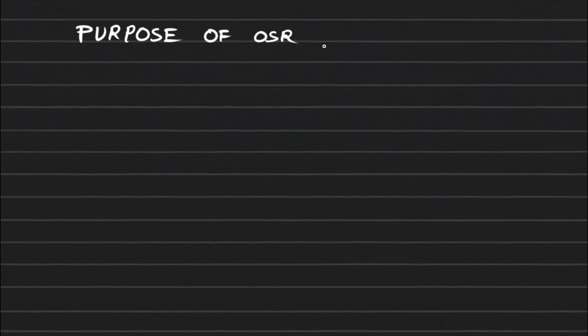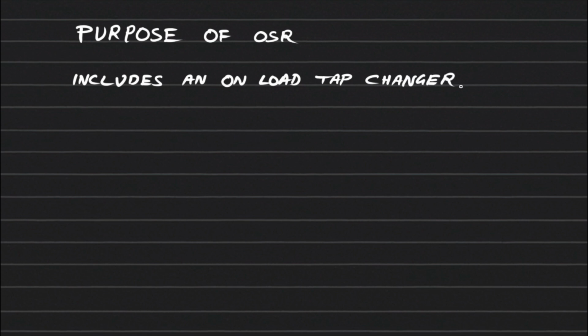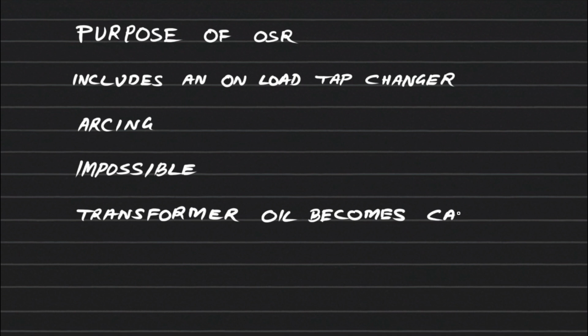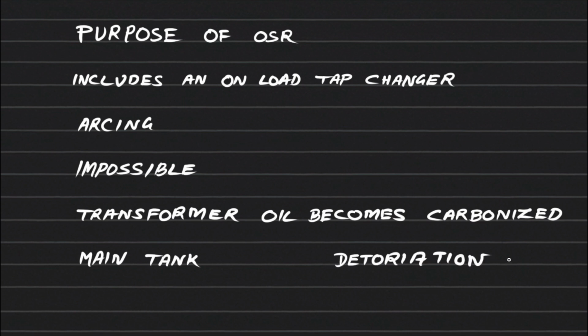Now, every modern power transformer includes an on-load tap changer, which allows the transformer ratio to be adjusted while it is in service. But during every tap-changing operation, some arcing occurs between contacts. Even though we try to make it arc-free, in practice it's impossible to eliminate arcing completely. Because of this arcing, the transformer oil becomes carbonized over time. And if this arcing happened inside the main tank, the oil quality would deteriorate very quickly.